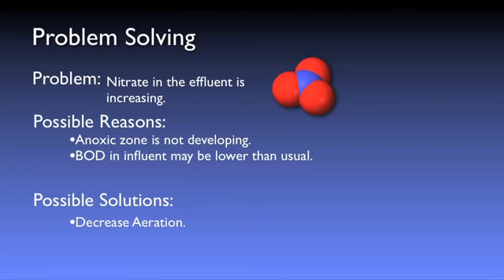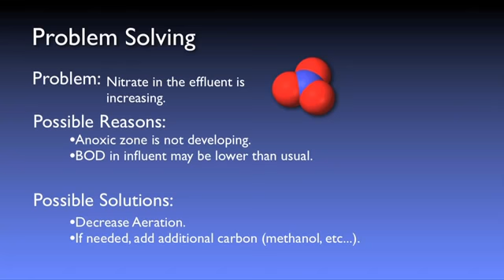If anoxic conditions are not being allowed to develop due to too much DO, decreasing the aeration will help in restoring these special conditions. If the BOD loading is unusually low, there may not be enough carbon for the denitrifying bacteria to perform. This less likely scenario would require additional carbon be added to the influent stream.